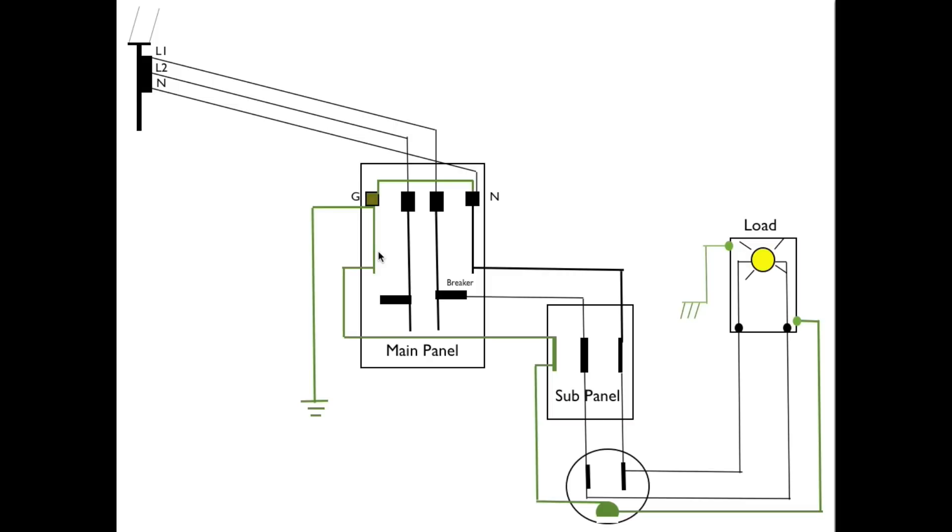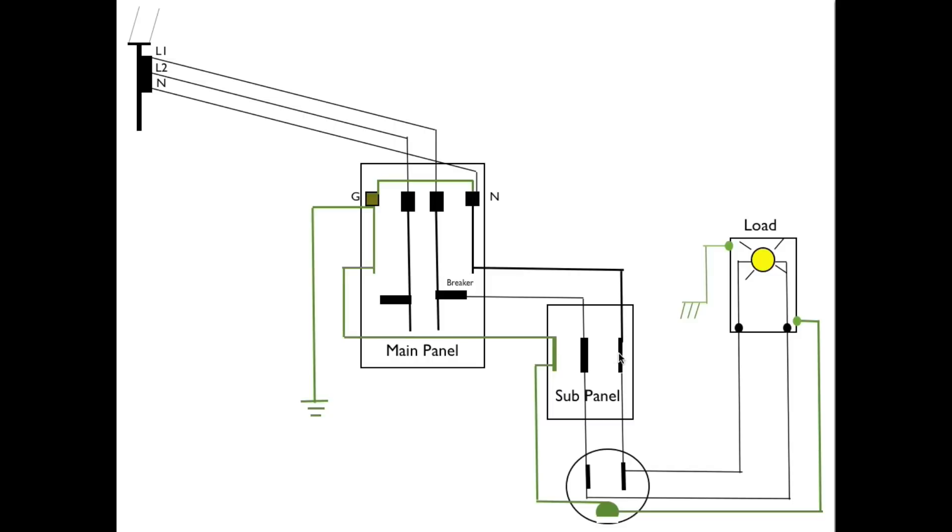Now I want to compare this main panel. I've got my two hots coming down to the terminals here and I've got breakers and then I've got a sub panel here. Okay the sub panel has the ground and the neutral wire differently. Notice that my ground bar here is not connected to the neutral.